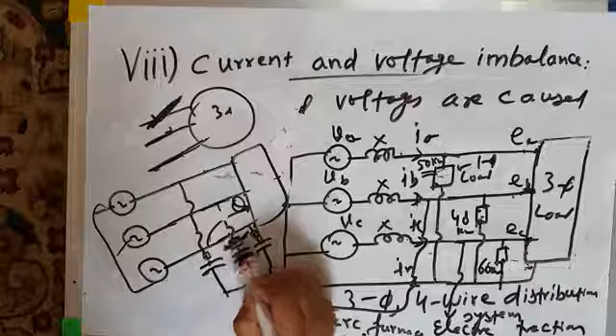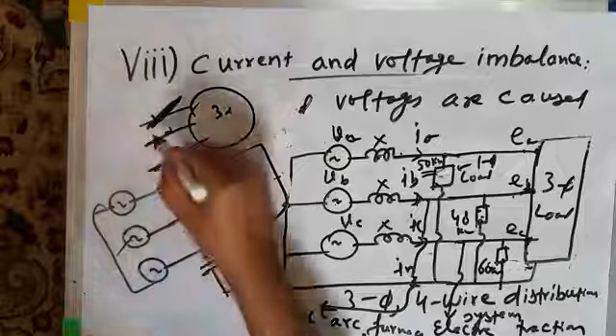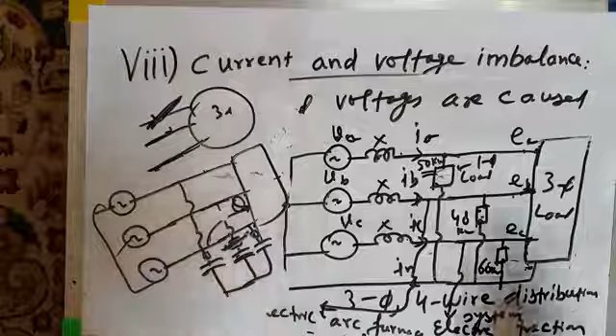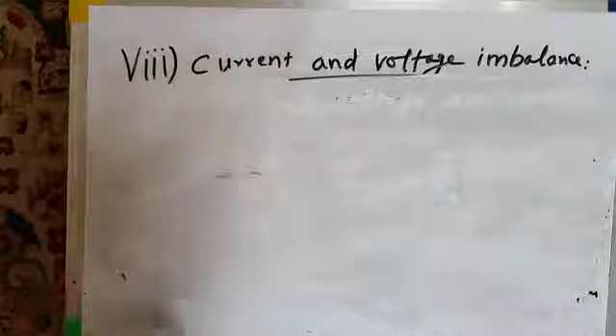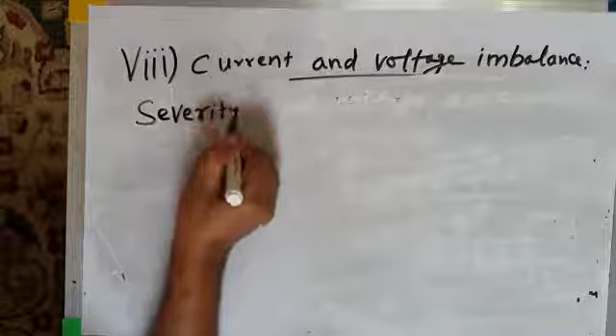So three main causes of voltage unbalance are: number one, non-uniform distribution of single-phase loads on a three-phase four-wire distribution system. Number two, malfunction of shunt capacitor banks, like blowing of the fuse of a shunt capacitor bank. And number three, single phasing of a three-phase induction motor. All of these are responsible for unbalanced three-phase voltages. Now there are three severity indicators for finding the severity of the unbalance. What are the severity indicators?